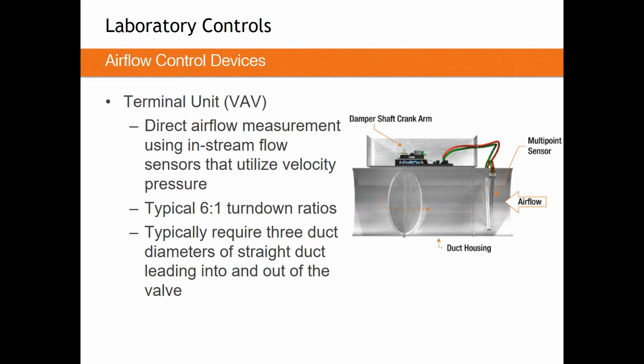Really, with the VAV box, one of the defining features, however, is the invasive airflow measurement. So you can see the multi-point sensor we show here. The airflow is directly being captured by that multi-point sensor. It's facing right into the airstream, looking right in the face of it. So any lint or dust or dirt or Kleenex or cardboard or plastic bags or anything in that ducting system can be captured by that multi-point sensor and unfortunately make it not do its job very well at all. In a critical application, it's extremely important that that doesn't happen. And a lot of times we're dealing with dirty applications here. So if you look at an isolation room or operating room, these are very linty and dusty places in the exhaust and return side of the system, and that multi-point sensor can become clogged up fairly quickly.